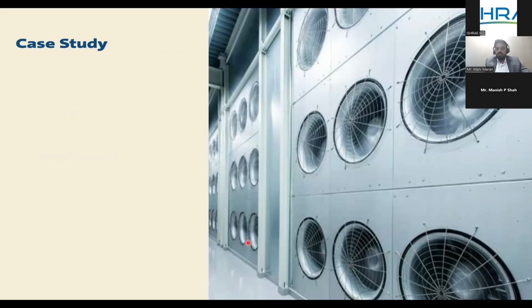And just to give you a number on what saving it can really bring in terms of kilowatt hour: the facility I'm referring to right now is a 3.3 megawatt facility which has a chiller as the primary device, and it has CRAH units and fan wall units. It's an air cooling based system. There is no CDU in this case study.